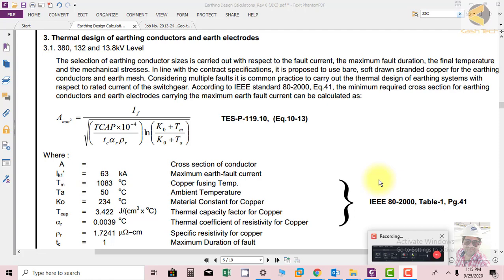Welcome friends, in this session we will study thermal design of earthing conductors and earthing electrodes. We have in our substation three voltage levels: 380, 132, and 13.8 kV. Selection of earthing conductors is carried out with respect to fault current.